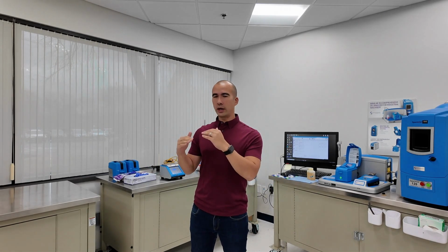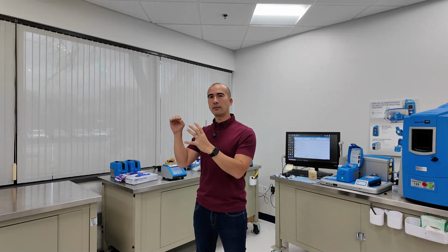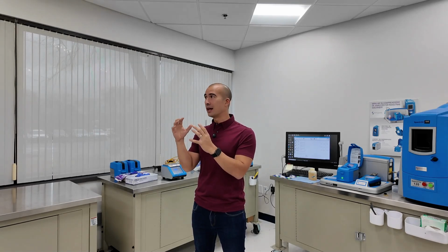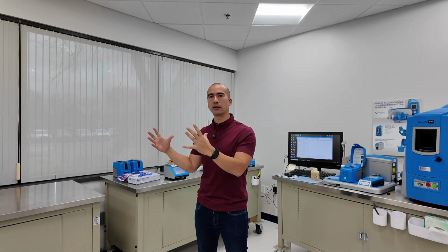Now, to me, we need to be viewing oil analysis in a similar way to what we do with some of the other condition monitoring disciplines. As an example, everyone is very comfortable with the idea that with vibration analysis, we have a number of different levels. If I have a very expensive gas turbine, I'll have a vibration sensor on the turbine, and that's picking up bearing faults. That's happening in real time and collecting data on a second-by-second basis. That makes sense because the value of that turbine is so high, we want to be able to detect any kind of fault instantaneously and potentially shut the turbine down.